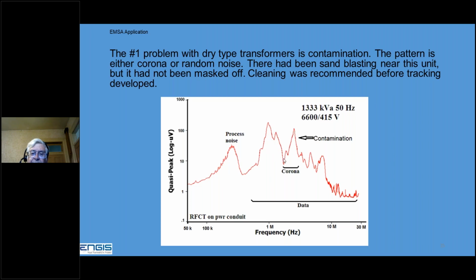We had corona peaks, 2 of them. Again, one at 1 megahertz and one of them a little bit higher, and that's from contamination. So 6.6 kV, that can track. So the recommendation was to take the transformer out of service when they could and clean it before they did get tracking. We did not see any tracking, just the contamination.